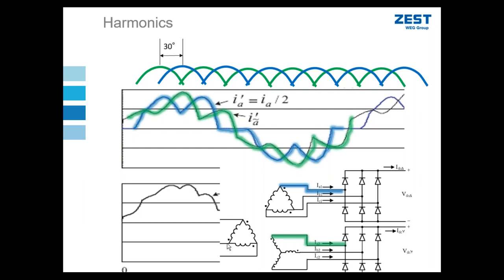These are connected to the same supply system by the primary. And so essentially at the input of this transformer primary, I superimpose these two waveforms on top of each other. So they are summed, they are added together. And my net result of that is the waveform that you see there. I'll clear the screen so you can see it a little bit more clearly. But essentially, if I'm now measuring the current in a single phase on the primary side of the transformer, I'm getting what looks like a much less distorted waveform, a much more sinusoidal looking shape than what I was getting on just a 6 pulse rectifier with no phase shifting techniques.